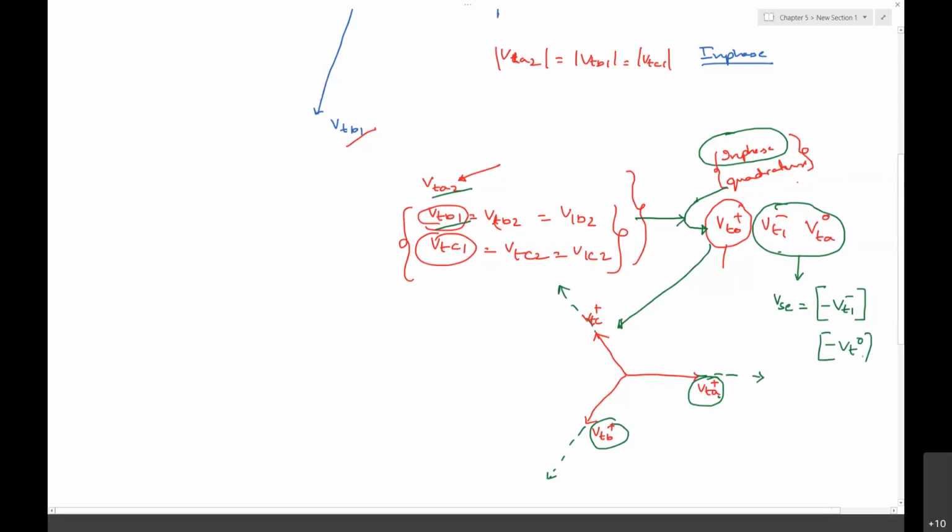That is how they achieve the in-phase or quadrature injection with respect to the positive sequence voltage, only for the unbalanced voltage sag condition. Otherwise, for a balanced sag condition, it is not required to resolve the positive, negative, and zero sequences.